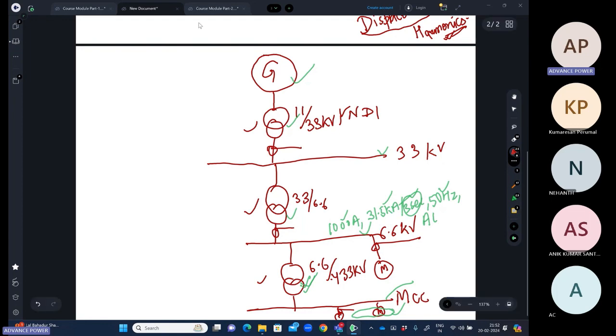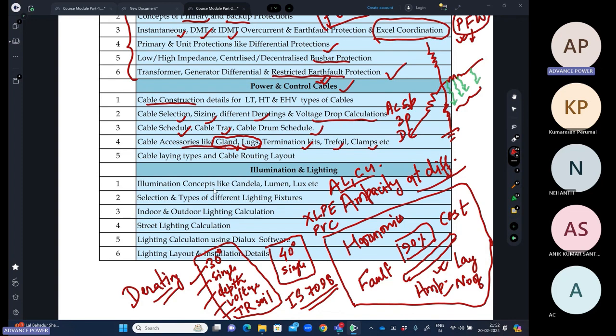And what are the criteria? For the cable, we select by the short circuit criteria, we select by the continuous rated current criteria, and we consider the voltage drop calculation. Based on that, we'll do the cable sizing. We'll discuss the cable laying types and cable routing.